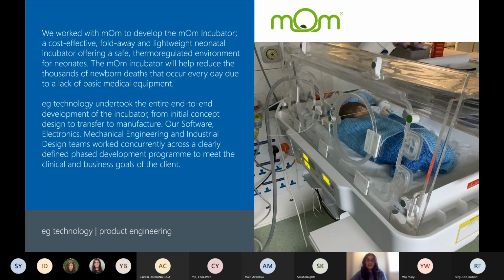I helped to design and write the code for the safety processor to ensure that the system stayed within the environmental constraints and trigger alarms if the environmental conditions were breached. For example, if the temperature went out of range, as this would be unsafe for the baby. Working on a device that can cause harm or death, this is classified as a Class C project. I had to ensure that the software I wrote was tested rigorously and documentation processes were in place.